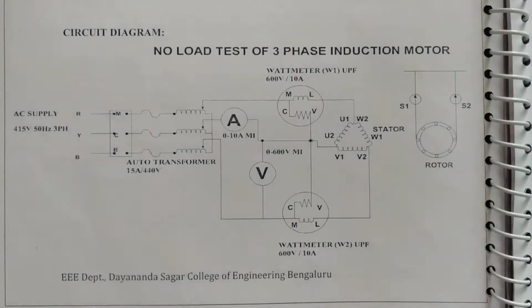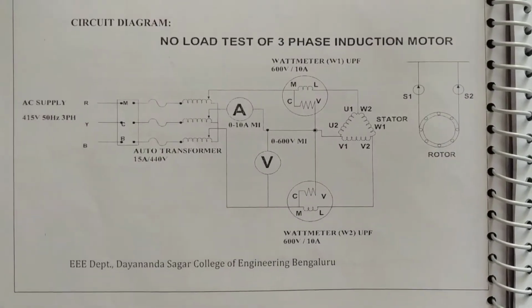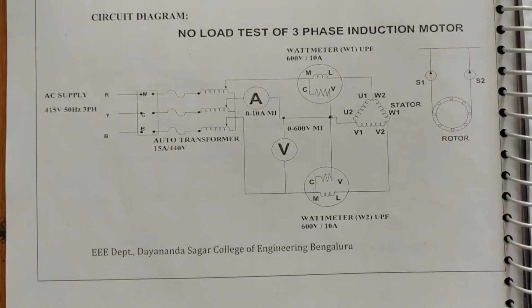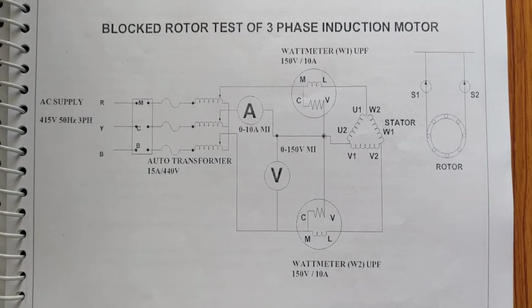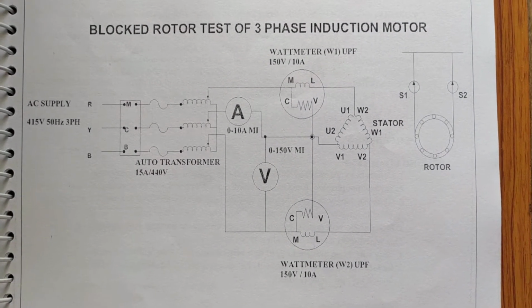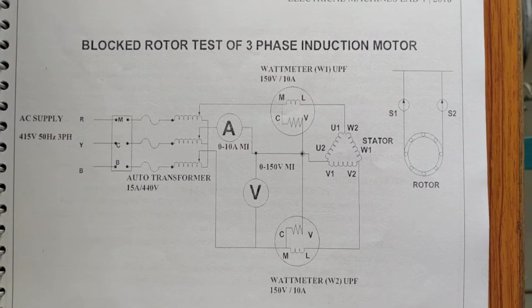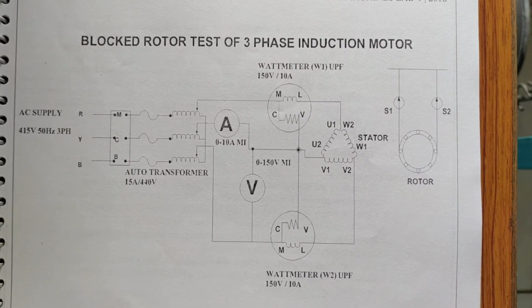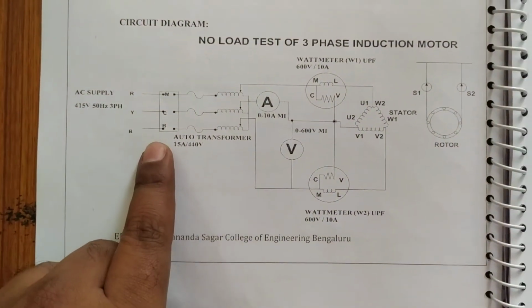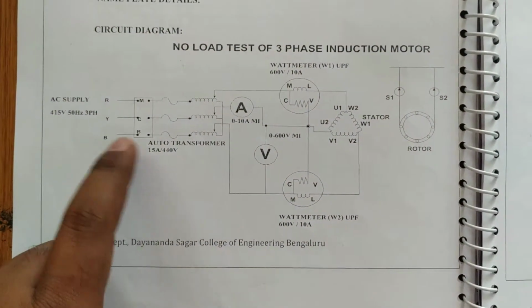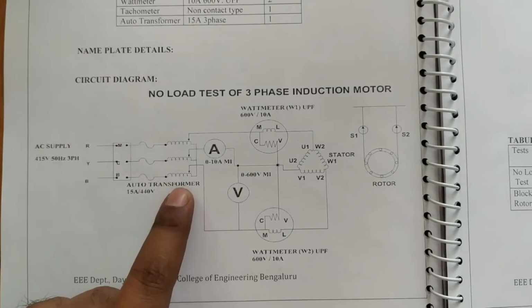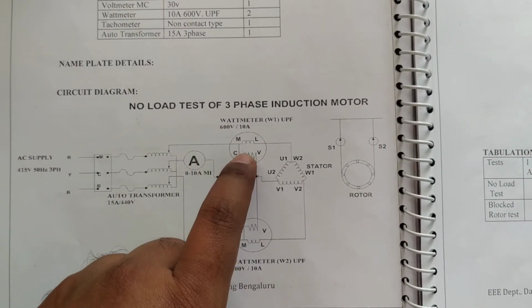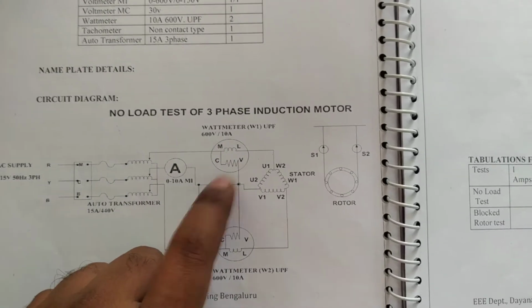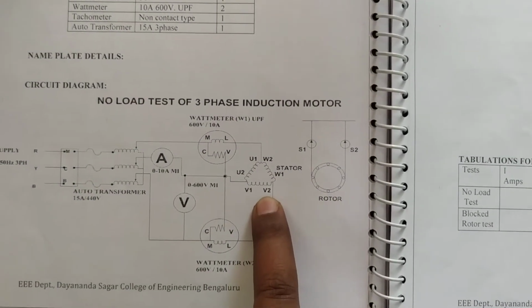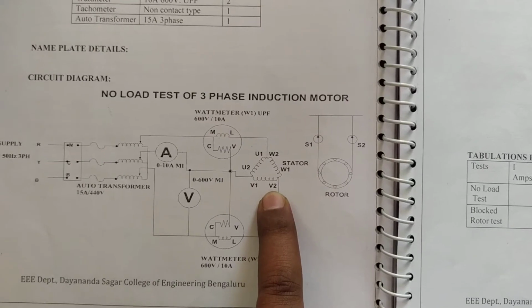So this is the overall circuit diagram which we use to conduct the no load test of a 3-phase induction motor. Even the block rotor test of a 3-phase induction motor has the same circuit diagram, except that we are blocking the rotor against rotation in this particular block rotor test. So here also, like in the case of no load test, we'll have a 3-phase supply auto transformer. Then the output of the auto transformer is given to the 2 wattmeters to measure the power, and then it is applied to the stator terminals of a 3-phase induction motor.